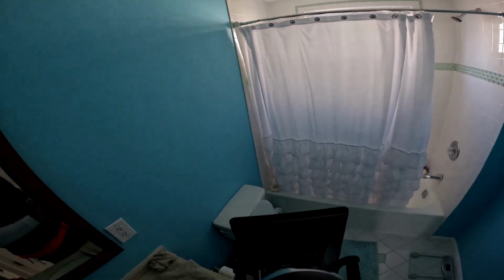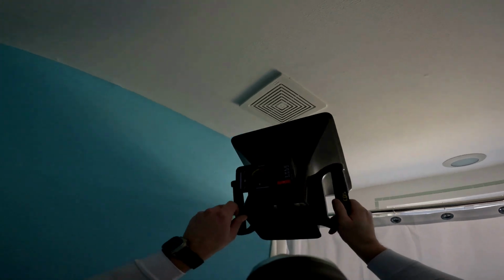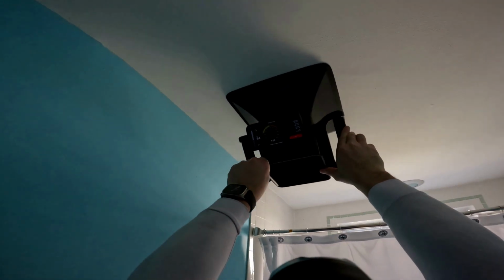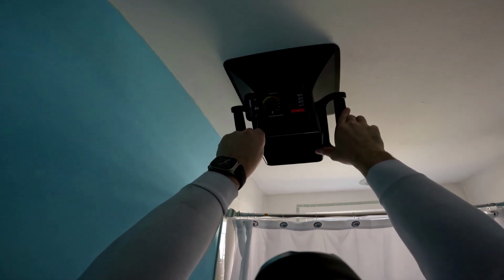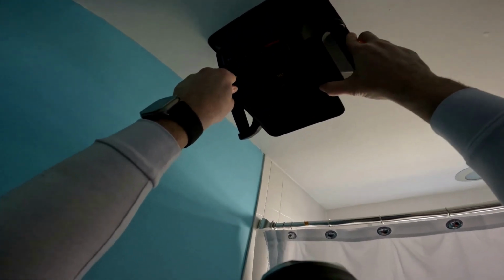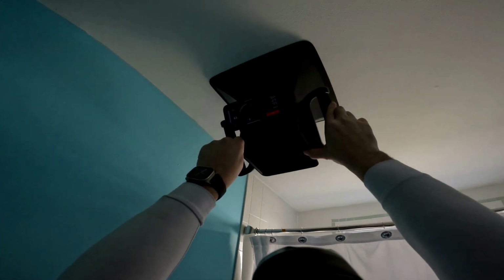So if I go into the master bathroom, and it's one of the furthest exhaust fans from the furnace, and I don't get a reading when I take a ventilation measurement, then I kind of know. I'm not saying I'm not going to go turn it on or anything, but it gives me an idea of what I should be looking for. Because sometimes, and I don't know if this is true for all energy auditors, the testing gauges and the ways they want you to do these things are a little difficult on the fly because there are a lot of fluctuations. So as much information as you can get about your surroundings before you get into the combustion testing, I advise you to do.